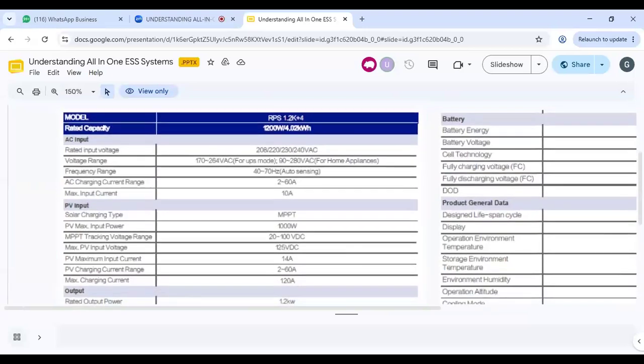So it depends on the one you want to choose for your appliance. It can tolerate a wide range of frequency, and it's auto sensing. Once the frequency is changing, it's following it up. It's not that it just senses that the frequency has reduced slightly from 50 Hz and then it will shut down. No, you can see it can operate from 40 Hz to 70 Hz, which is quite wide. Then you look at AC charging current, up to 60 amps. Then look at the maximum input current, which is 10 amps. All these are part of the rating.